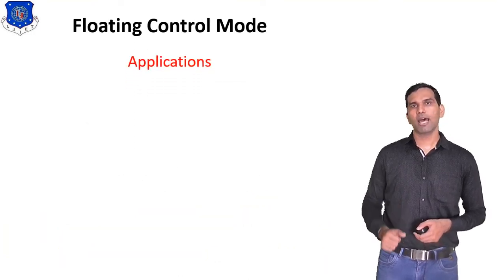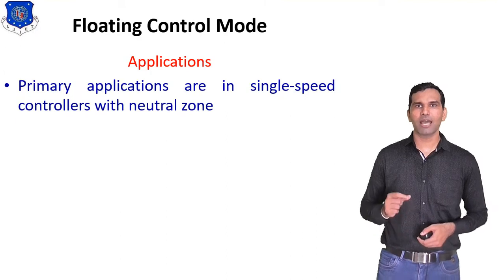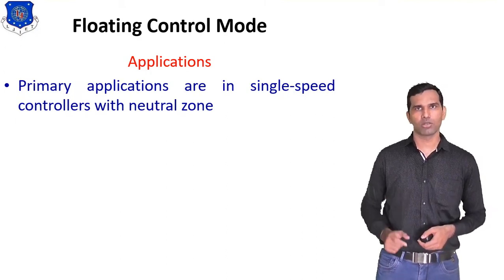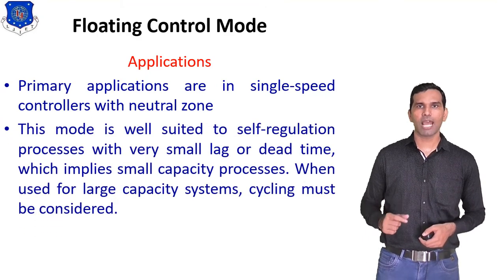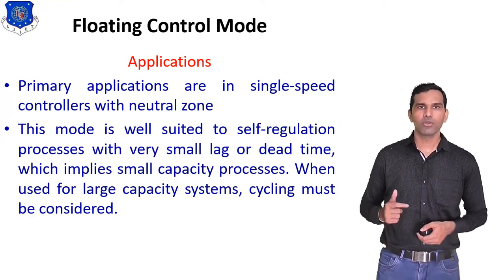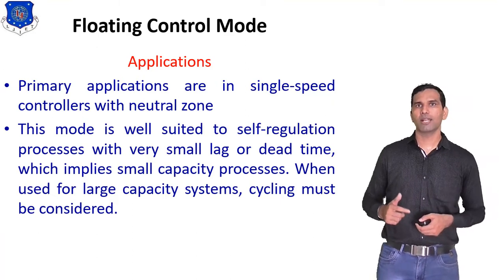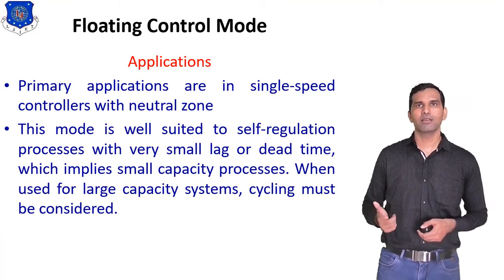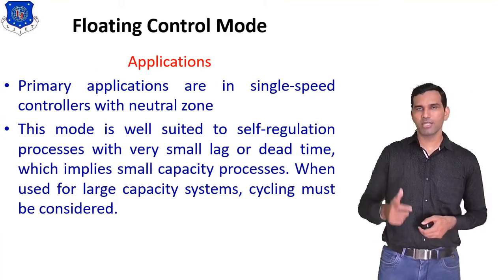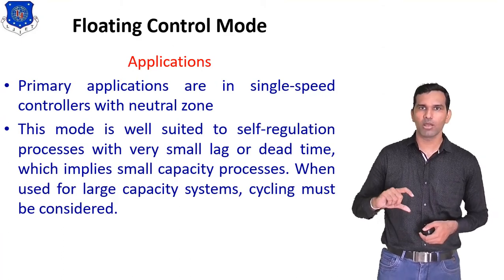Now, the applications of floating control mode: the primary application is a single speed controller. This mode is well suited to self-regulating processes with very small lag or delay time, which implies small capacity processes. When used for large capacity systems, cycling must be considered.